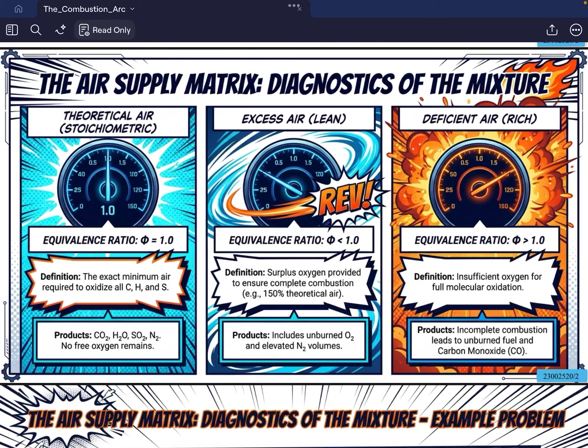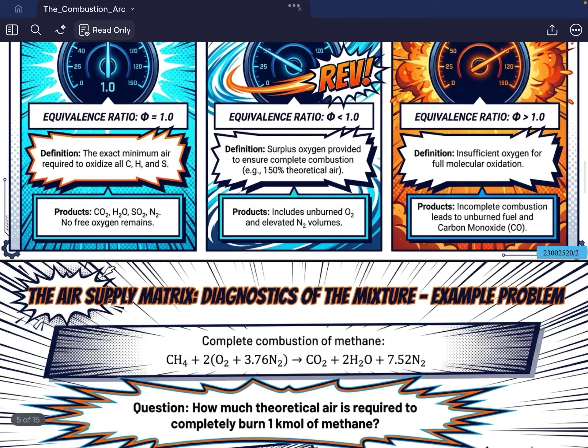And the third scenario is deficient air or rich combustion. Here, the equivalence ratio is greater than 1. There is insufficient oxygen to completely burn all fuel molecules. Consequently, incomplete combustion occurs. Unburned fuel may remain, carbon monoxide can be formed, and other undesirable species may also appear. Rich combustion generally reduces efficiency and increases pollutant emissions. Therefore, one of the most important responsibilities of engineers is controlling the air-fuel ratio so that combustion occurs under the desired operating conditions.